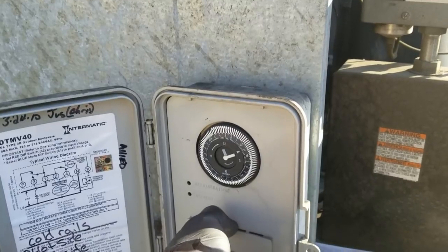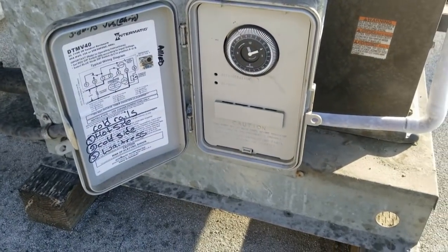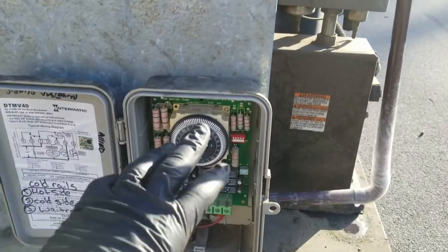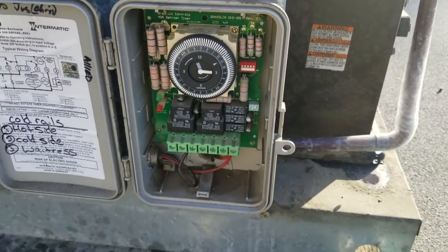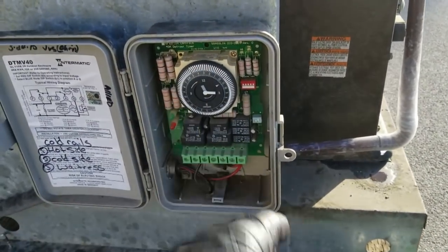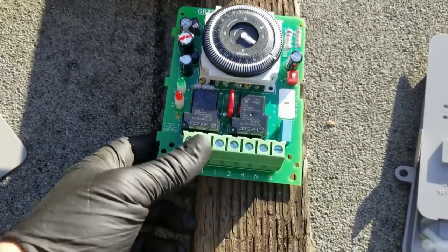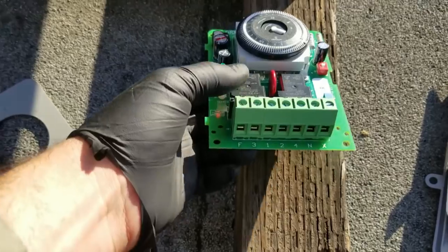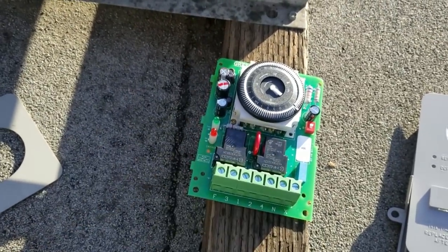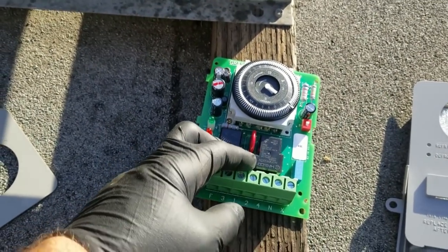This is going to be an easier one. I'm going to pull that defrost clock apart and replace it. I confirmed it has 208V going to it — that's correct — and I went ahead and shut off the breaker. A little review on this clock: this is a DTMV40, a standard electromechanical defrost clock. It uses sets of relays instead of just the mechanisms in the clock so it can handle higher amperages — you can even run a compressor through this.